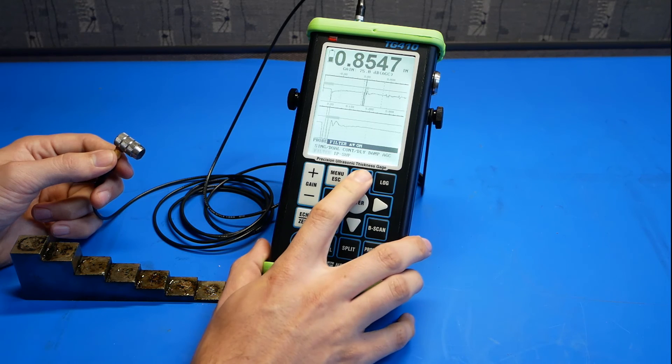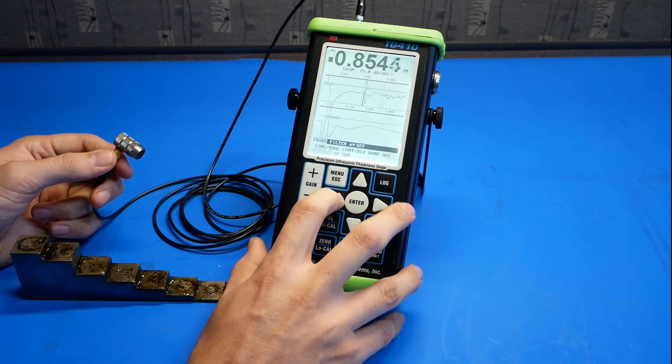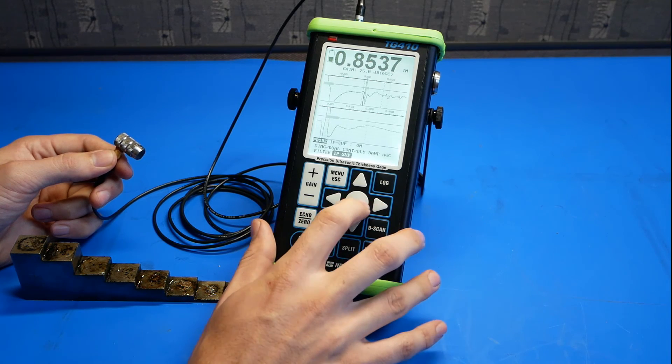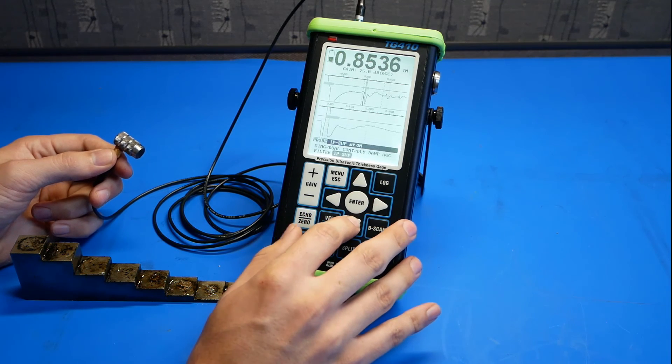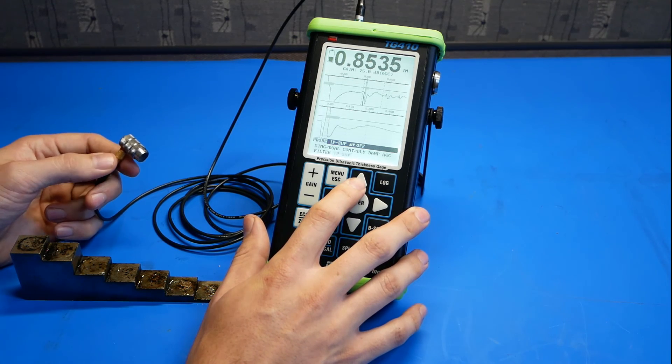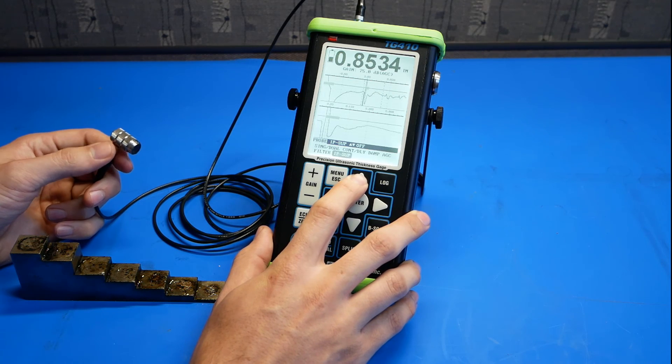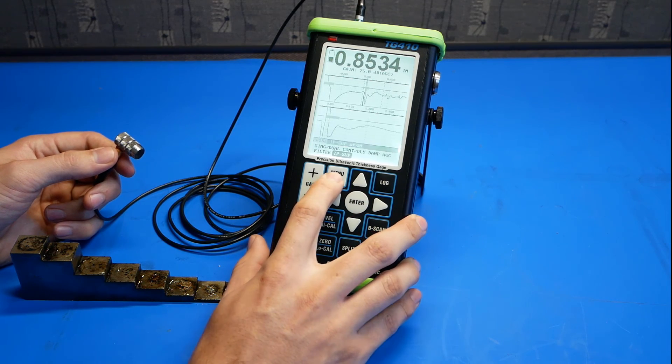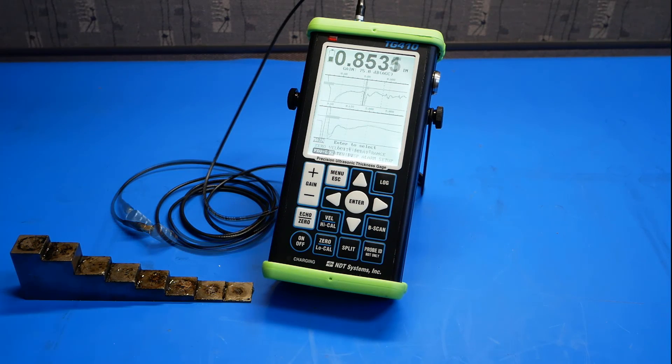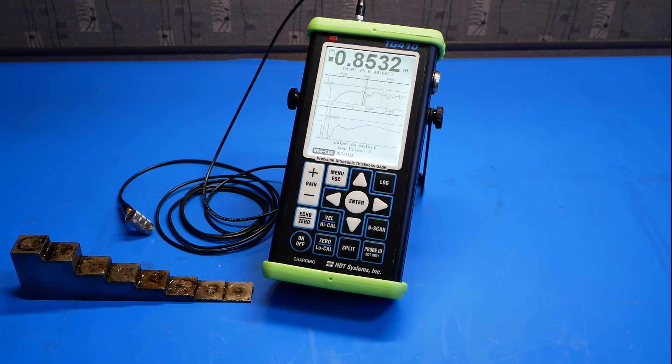Filtering, we can turn on and off. These help with bandwidth. And initial pulse suppression, which keeps the initial pulse from being too noisy. This probe is pretty clean in signal, so the suppression doesn't help much. Now, that's all for setting up the probe. That's all for this video. If you have any questions about the gauge or potential applications, please contact us at our website, ndtsystems.com. Thanks.